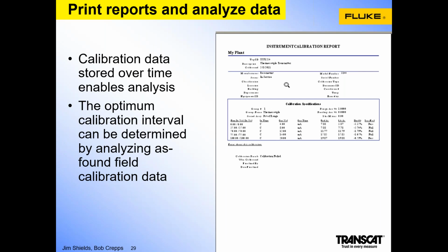One of the big advantages, of course, is being able to access that data, being able to print it and provide that information to an auditor or quality inspector. That data over time enables analysis. And by virtue of comparing that information over time, intervals can be determined by analyzing the as found results before the adjustment is made. And if the errors are small on your as found, perhaps this device could be a candidate for having its interval extended.